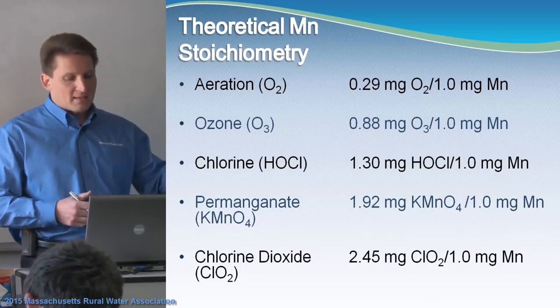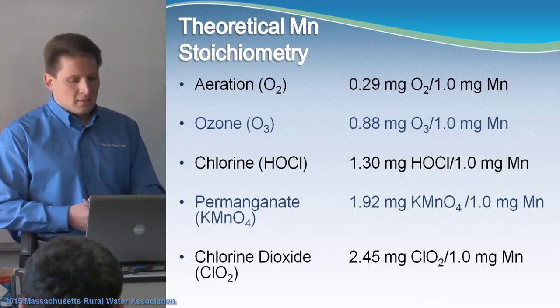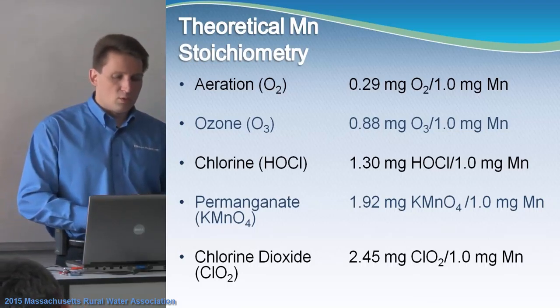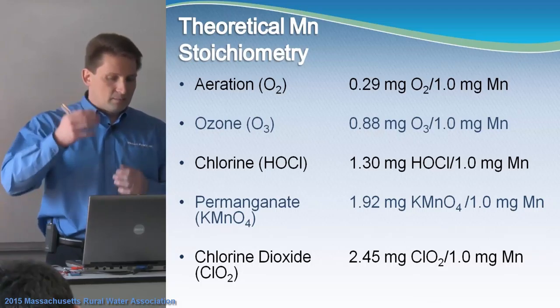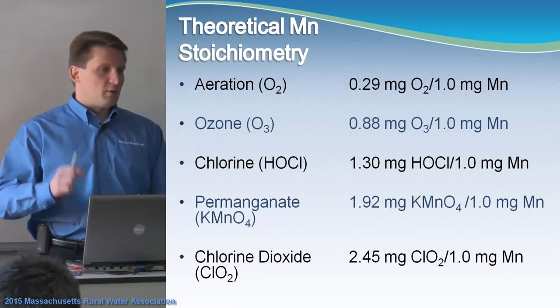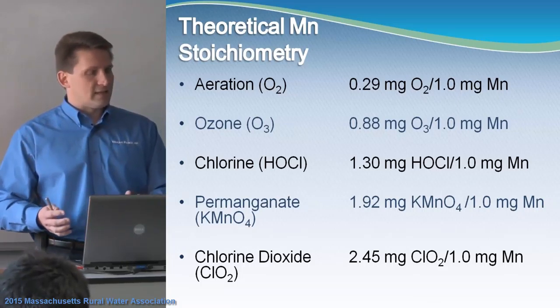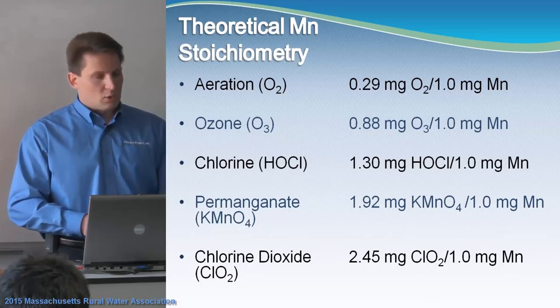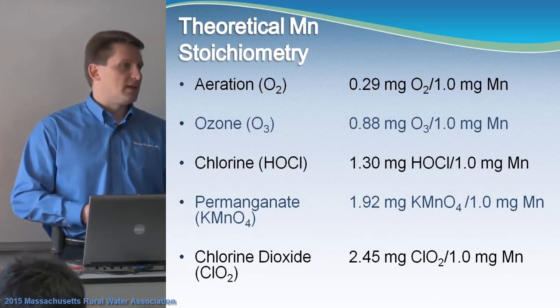This is the stoichiometry — basically how much mass of an oxidant you need per unit mass of manganese. The most common oxidants in drinking water are aeration, ozone, chlorine (hypochlorite), permanganate, and chlorine dioxide. For aeration, you need about 0.29 mg of oxygen per mg of manganese. For ozone, about 0.88 mg/mg; chlorine, 1.3 mg/mg; permanganate, 1.92 mg/mg; and chlorine dioxide, 2.45 mg/mg.